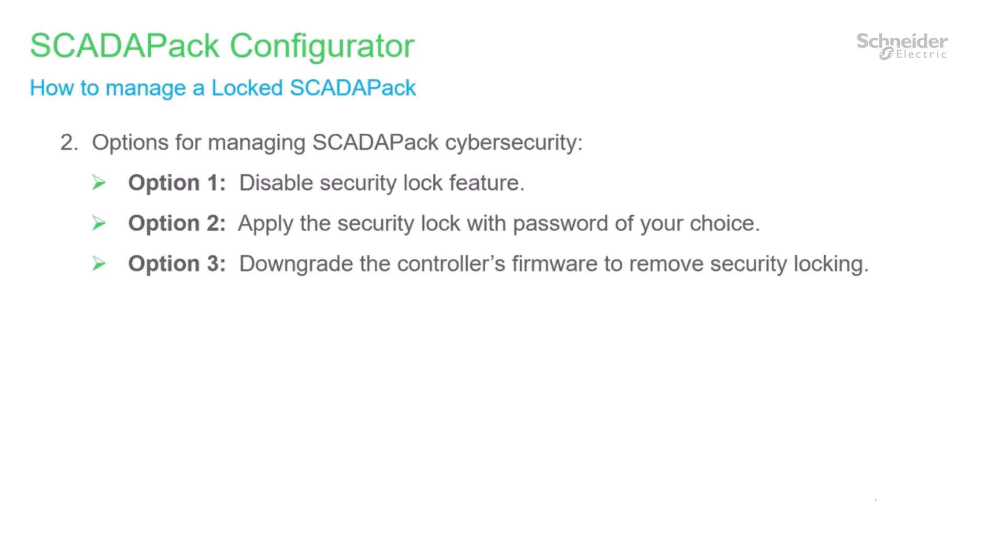Typically, you may want to begin with option 1 to disable the security lock because you will need to have the controller unlocked in order to edit and write configuration changes to it. You may choose option 2 to apply the security lock later after all configuration is completed and the device is placed in the field. The security lock blocks all configuration commands, but protocol access is not blocked to communications with other devices or with the SCADA host.